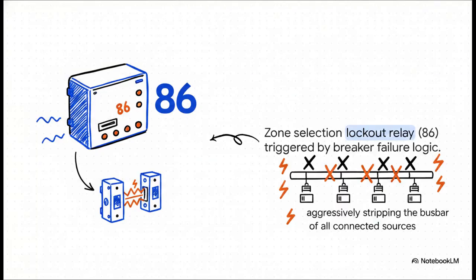And this is where the digital logic meets physical hardware through the 86 lockout relay. When the breaker failure logic triggers, it usually hits one of these zone selection lockout relays. The 86 relay physically executes this massive backup command, stripping the busbar of all connected sources to clear that persistent fault once and for all.